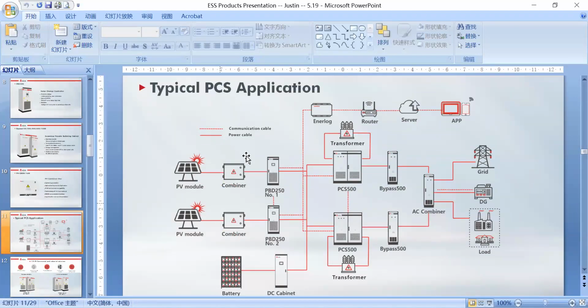Okay, now let's say in the middle. For this application, we use 2 PCS 500 in parallel. That means the peak load for this application is not larger than 1 megawatt. Okay, so the rated power of our PCS has to be higher than the peak load of the application. Okay, and our installation transformer connects with our PCS. Then let's have a look at our left side. Our left side is our DC power side. Okay, all the power is DC power. Okay, from the PV panels, to our PV combiner box, then connect to our PBD 250.